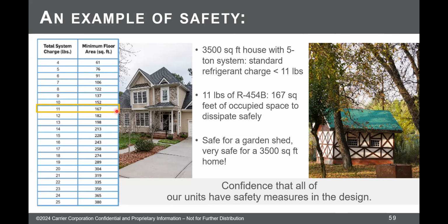Like only 16 by 10 is the whole building, and you have 11 pounds of refrigerant. What are you doing in this building? What illegal activity do you have going down, right? It's not going to be hard at all. So for residential splits, commercial splits, rooftop units, it's super easy. You're going to be no problem. Mini splits, no problem. The time it's going to be a problem is when you have multi-head systems.